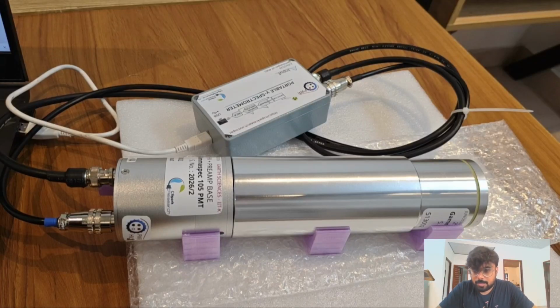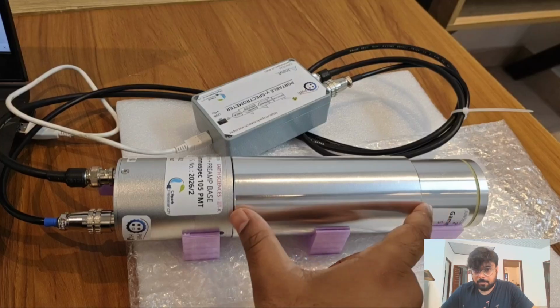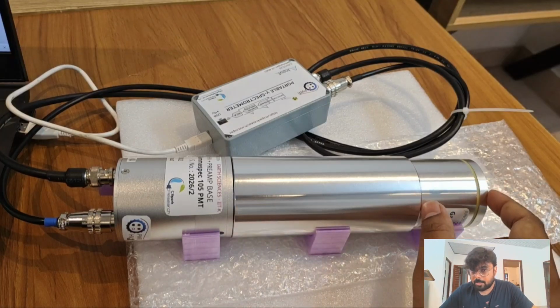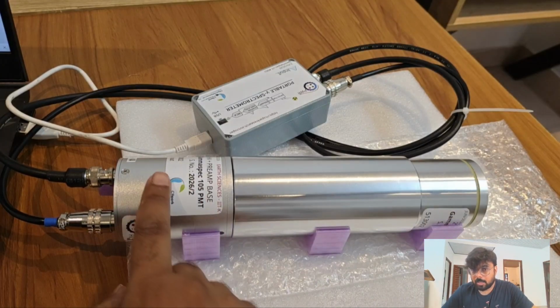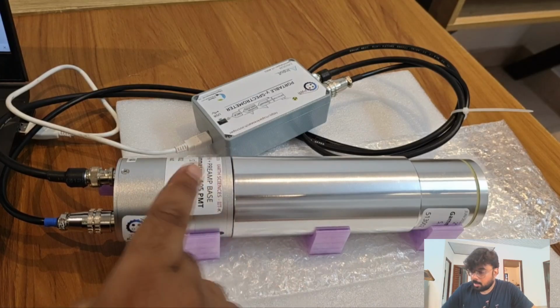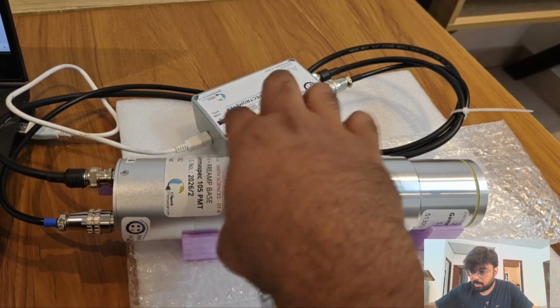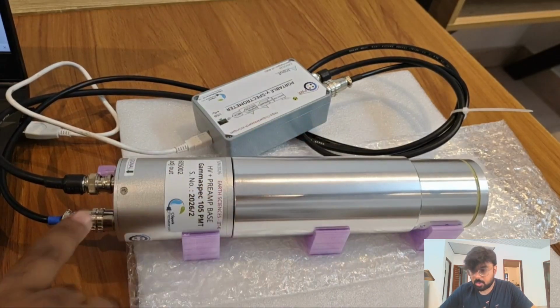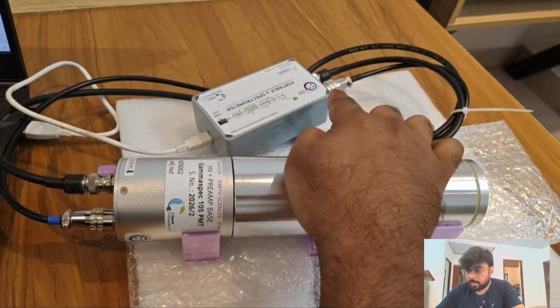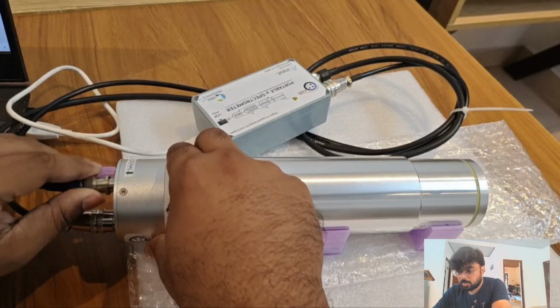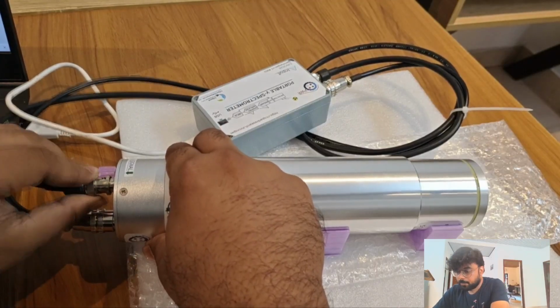Hi, so this is a quick introduction to using the gamma spectrometer. This unit has the PMT, the 2-inch sodium iodide scintillator coupled to the PMT, and this is the HV electronics. From here you have the BNC connector, which is labeled signal, which you're going to use to connect to the multi-channel analyzer. So this is a BNC cable, which means you twist it like this and then remove it.